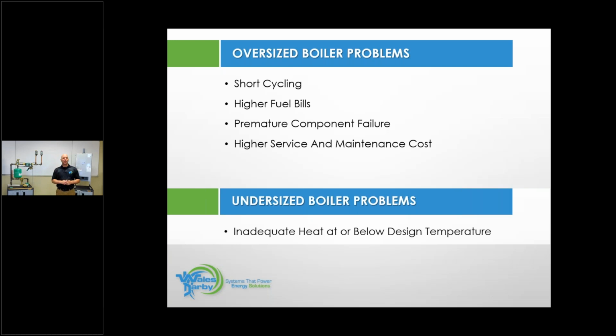If we oversize a boiler, it's going to short cycle. What does that do? It drives up the fuel bills, premature component failures, and just higher service and operational costs. We don't want that for anyone. And don't guess. Don't just say, you know, that boiler's twice the size it needs to be. We're going to put in this because this is what I do every day, and it works. If you undersize a boiler, it's going to inadequately heat the home at design temperature or maybe more often than that.